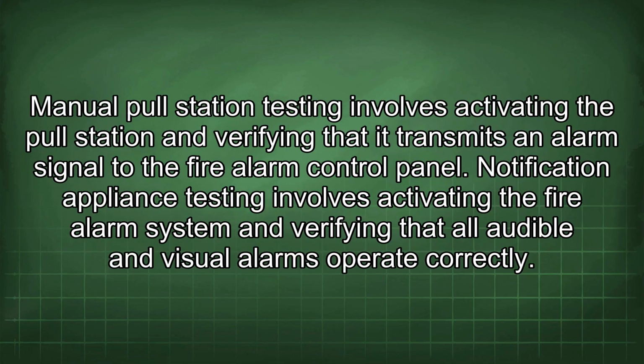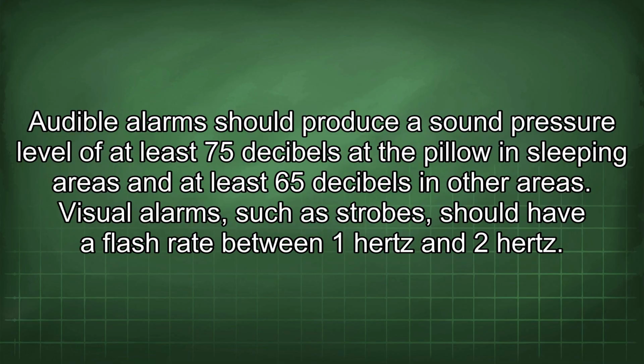Manual pull station testing involves activating the pull station and verifying that it transmits an alarm signal to the fire alarm control panel. Notification appliance testing involves activating the fire alarm system and verifying that all audible and visual alarms operate correctly. Audible alarms should produce a sound pressure level of at least 75 decibels at the pillow in sleeping areas and at least 65 decibels in other areas. Visual alarms, such as strobes, should have a flash rate between 1 Hz and 2 Hz.